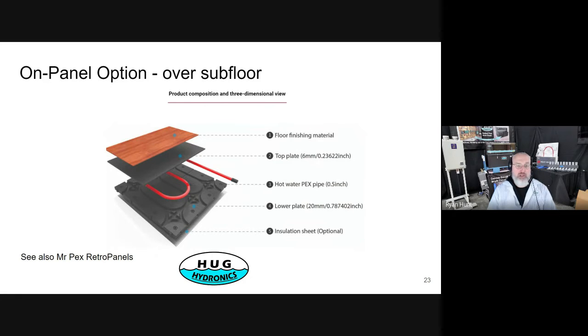The on-panel option is another variation of that, made in plastic. Mr. Pex's retro panels are another example. They have a lot of flexibility for how you can route those things in there. And it has a plastic cover that gives it a nice smooth look, but there are seams between them. So generally you put a floor finishing layer above that. Now, this is one of those systems that requires 6-inch on center spacing because the heat doesn't spread sideways through the plastic very well. So you put the tubes more close together and you get a more even surface temperature that way, more even heating.